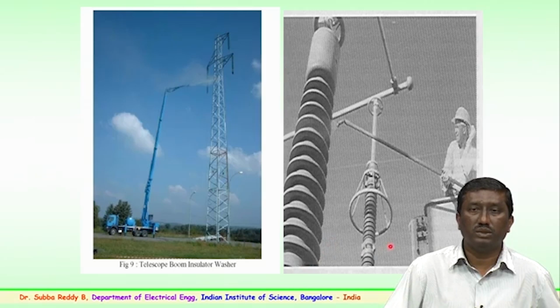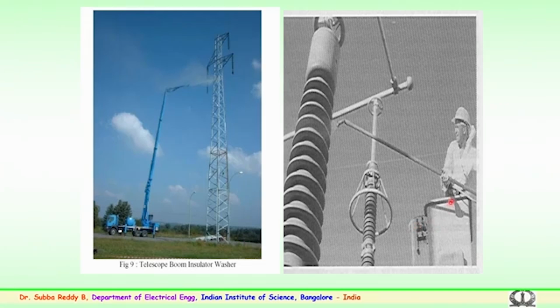The technician or the person who does the operation is on a particular insulated arrangement, where he uses the water jet to clean the post insulator, particularly in the substation, or the bushings of the CTs, PTs, and several of these things. These contaminants which spread over a time period have to be properly addressed, that is cleaned, so that during monsoon conditions the surface of the insulation does not become wet and start conducting. To arrest the conduction, proper cleaning of these contaminants or pollutants is essential.